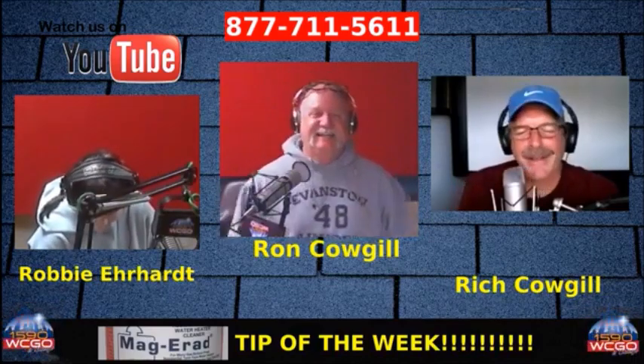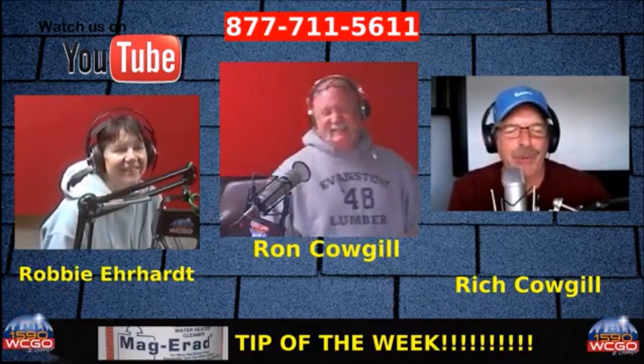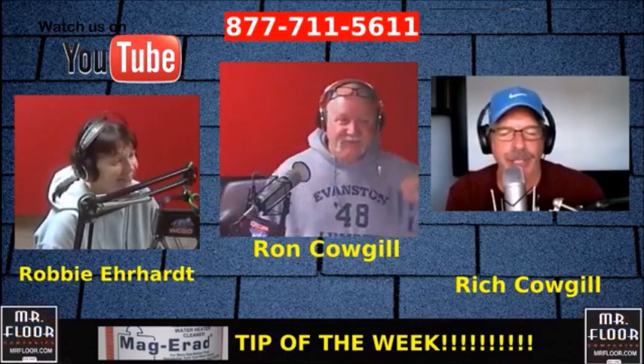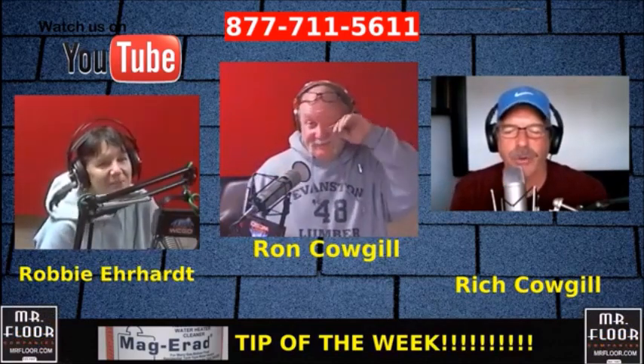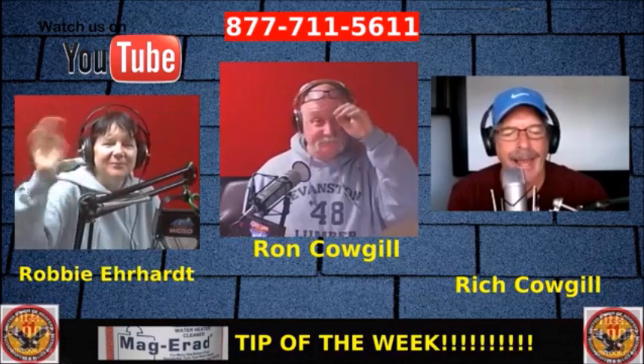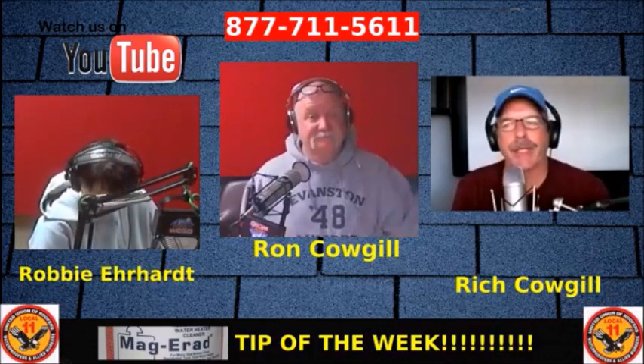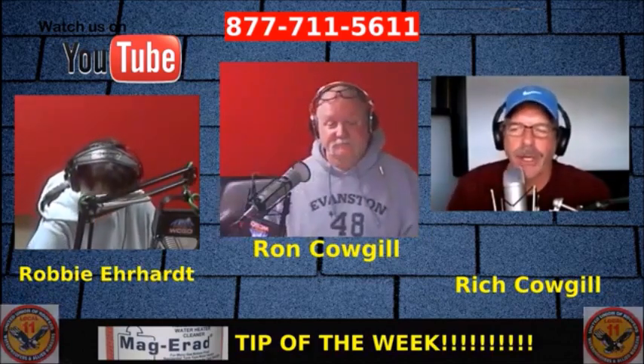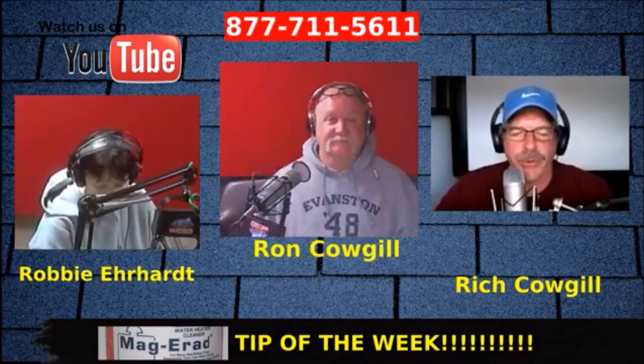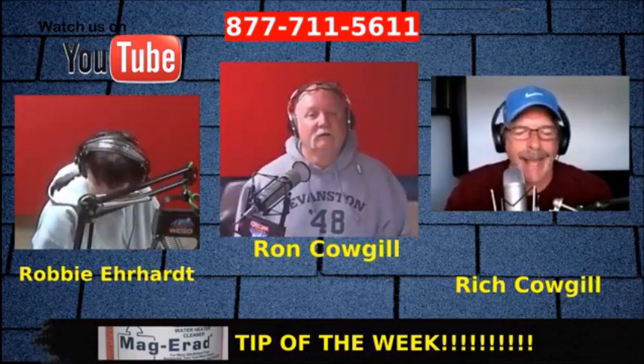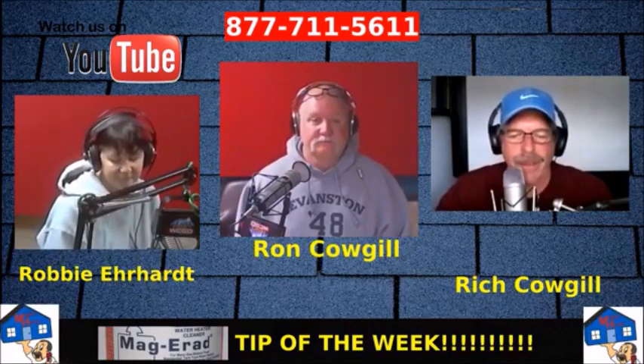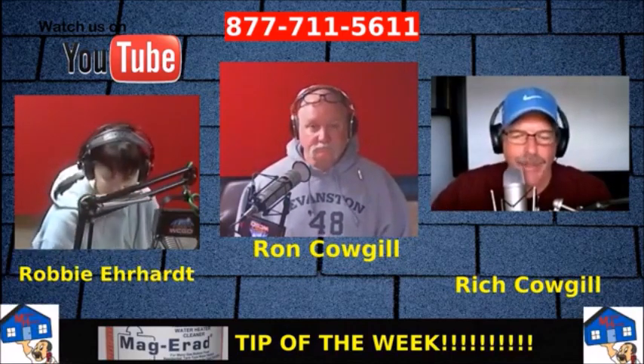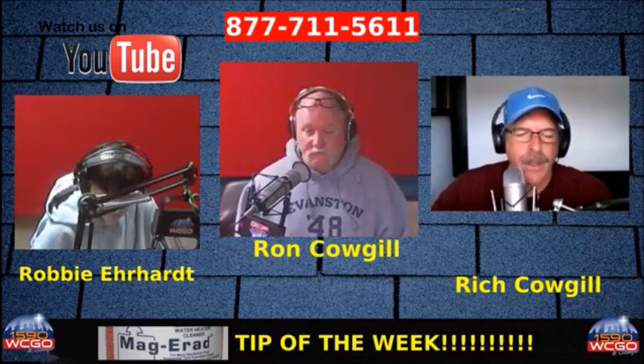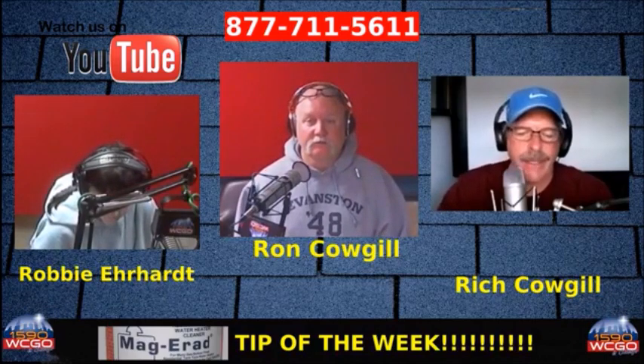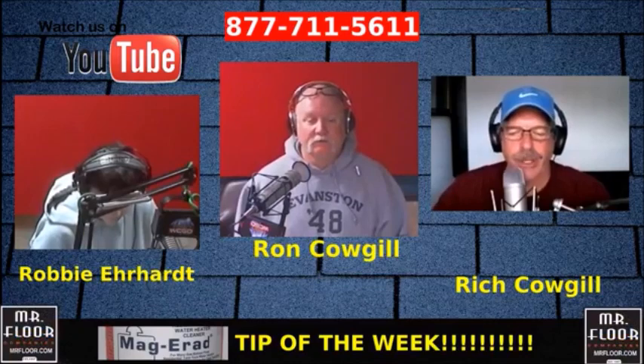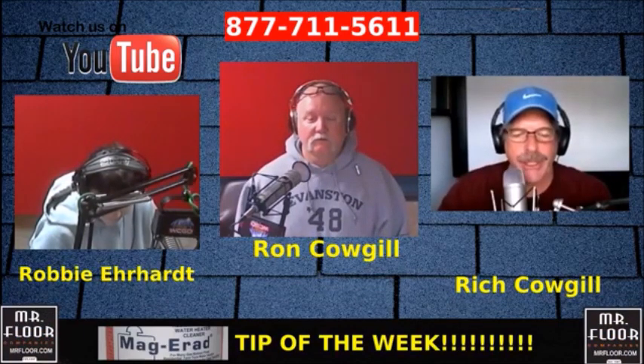Enough, this is the only serious part of the show we have in 3 hours, and you're making this difficult. So you need to do a Manual J. The Manual J calculation is to determine the heating and cooling loads of your home, and that will then get you in the direction. Once you know the loads, you can figure out the tonnage or BTUs of the equipment you need. Manual S is how you select the equipment so that it becomes the right size, or it is the right size. Manual D is a method used to determine the overall duct layout, including individual duct sizes.